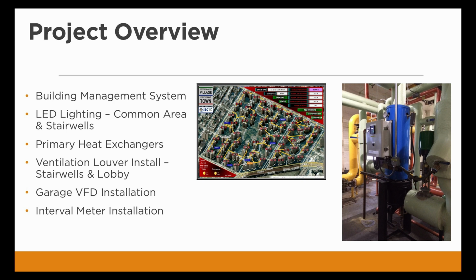Garage VFDs were another low-hanging fruit project. We were running exhaust fans in 6 garages — 16 fans running 24/7 — and nobody ever complained about them running constantly. The second we put them on VFDs and carbon monoxide detectors, people started going into the garages and shutting down the fans in the middle of the night.